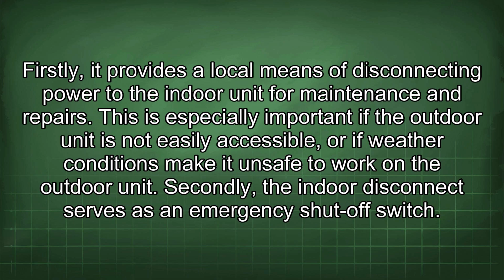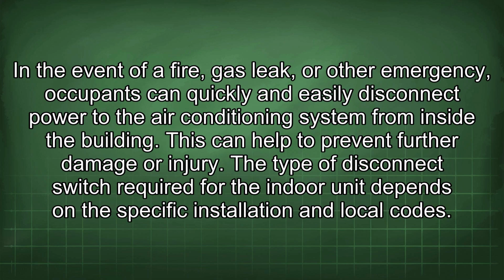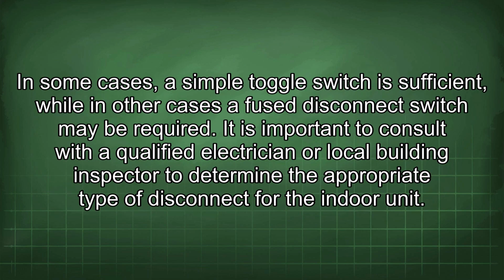Secondly, the indoor disconnect serves as an emergency shut-off switch. In the event of a fire, gas leak, or other emergency, occupants can quickly and easily disconnect power to the air conditioning system from inside the building. This can help to prevent further damage or injury. The type of disconnect switch required for the indoor unit depends on the specific installation and local codes. In some cases, a simple toggle switch is sufficient, while in other cases a fused disconnect switch may be required.